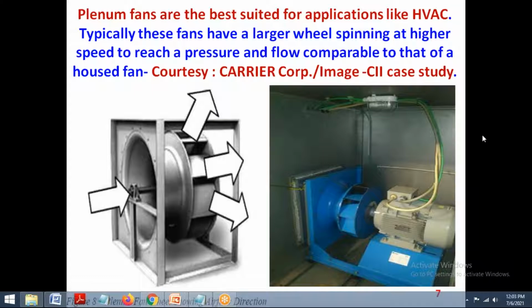If you replace the existing impeller with a plenum fan or a plug fan, this is an excellent fan. It is more or less like an aerofoil fan, but the outer casing is not there, and it operates at high volume and low pressure, and this will deliver excellent efficiency. We will see in depth. That is what the CII case study or Carrier Corporation says. We can replace the existing blower with this plug fan or plenum fan, and automatically you can see an efficiency improvement of more than 20%.